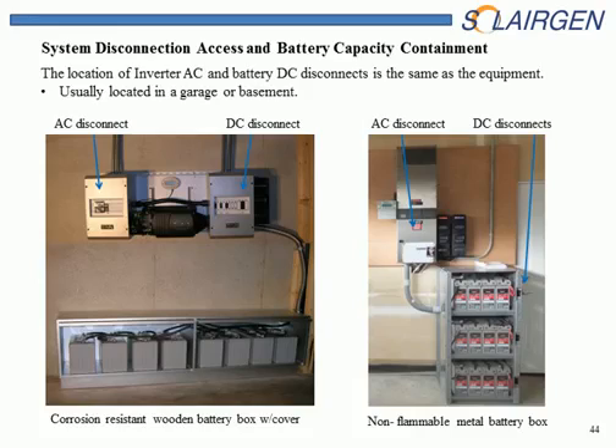So what we're looking at is lead acid batteries, typically in enclosures. If not, you have to get the water level above the terminals. Terminals are usually protected. If you had falling debris, metal debris falling on top of it, you could get a short on it, so there's potential for that. But generally they're isolated safe.